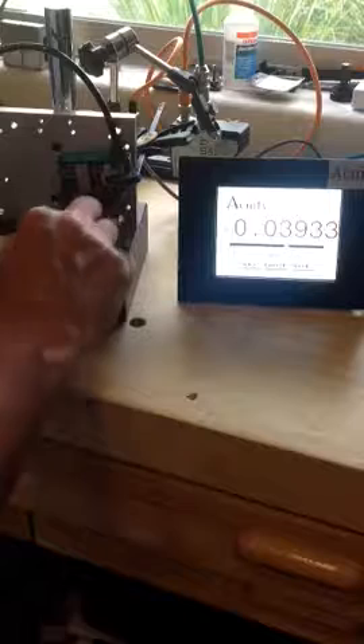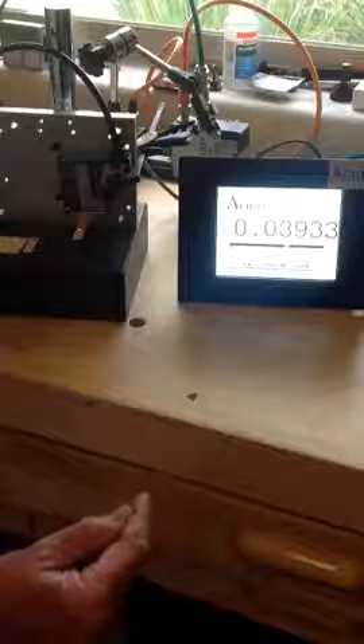It is also possible to set up an offset where we would simply add in a 0.03937, right, to the number. So we would create another 0, would add in that number, and it would force it to this exact number to help compensate for any temperature, pressure, humidity changes. And so at the start of every shift, the operator would typically put the gauge block in, do the quick 2-point cal with the offset, and it would correct for this last 2 to 3 tenths of a thousandths, which is a lot of just mechanical creep and mechanical movement of the fixturing.